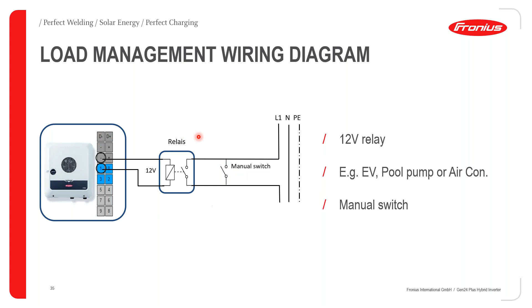Once these conditions are met, a 12-volt signal will be generated on the pre-configured port. This energizes the external relay, and the contact of this relay is then used to energize the appliance we want to power, doing so in a smart way by making use of the surplus energy generated from the PV. You can also have a manual switch to effect a manual override of this external relay.